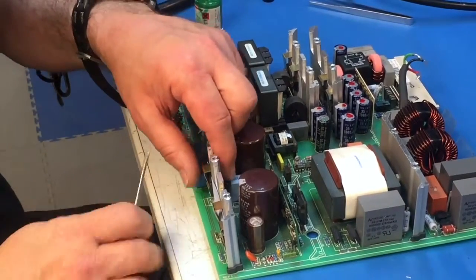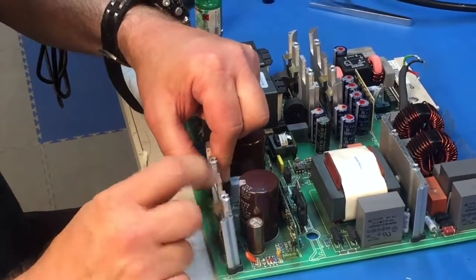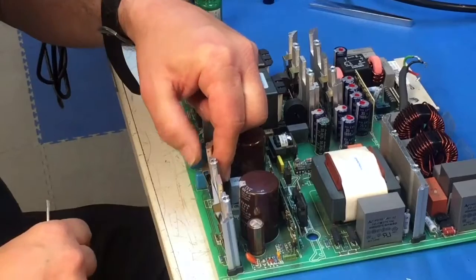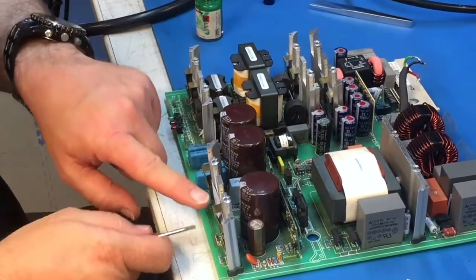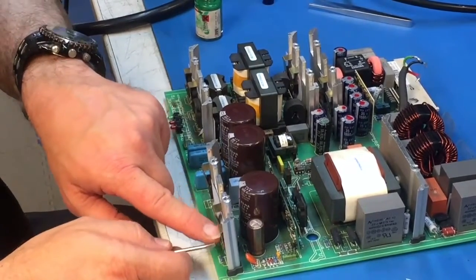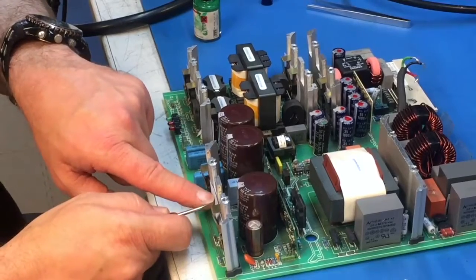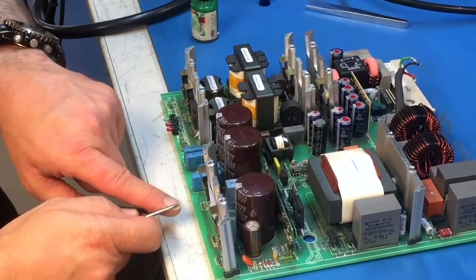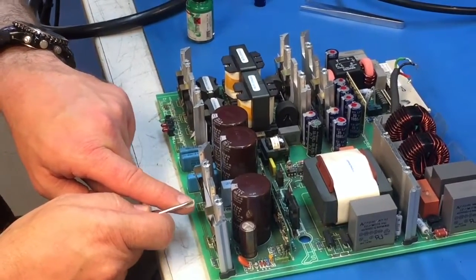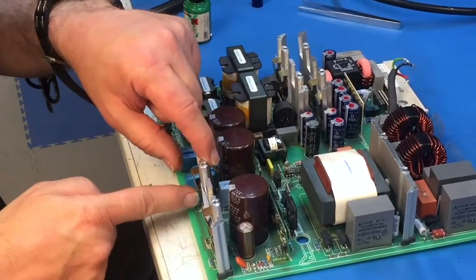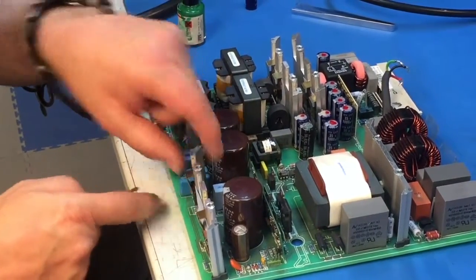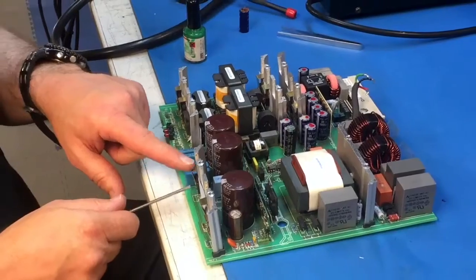One problem we know of is these clips can crack or lose tension, and that one's a bit loose. And also the thermal conductive pad underneath can puncture, and that causes insulation failure, and that will cause the power supply to fail. So these will be removed, checked, and put back into position and replaced where required.